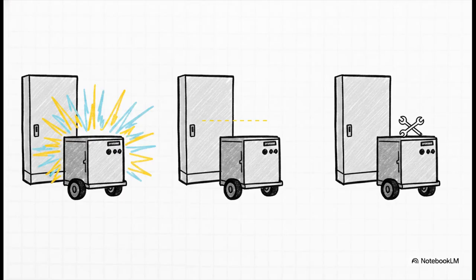For those draw-out types, engineers actually use 3 distinct physical positions to interact with them safely. In the connect position, the breaker is fully pushed in, making contact with the high-voltage bus bars. It is live and operational. In the test position, it's pulled back just enough to break the main high-voltage circuit, but the low-voltage control wires stay connected so engineers can test the mechanical tripping safely. Finally, in the isolated position, the unit is pulled out completely, entirely separated from all power for full hands-on maintenance.